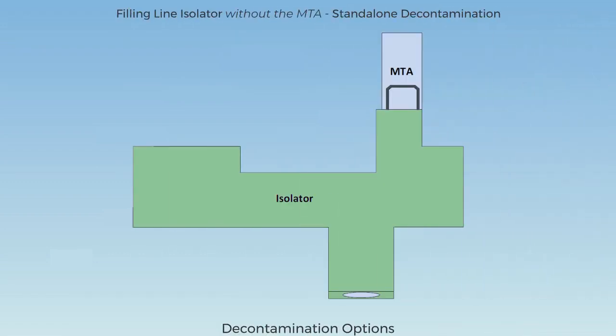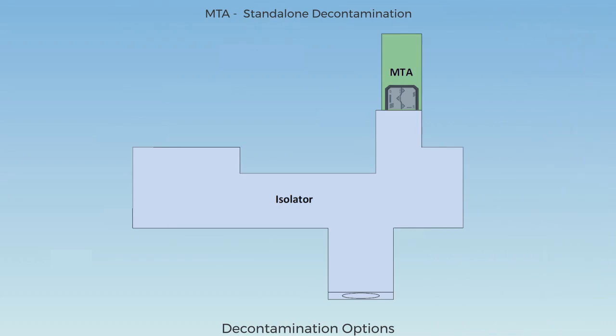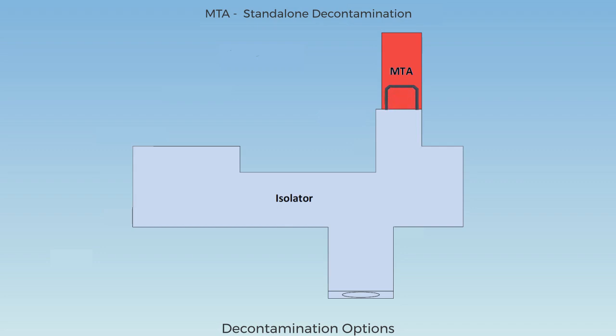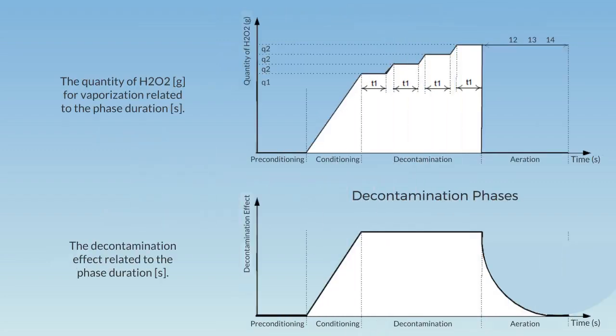The next decontamination option is the filling line isolator without the MTA. After start of the standalone decontamination cycle, a leak test will be performed. The transfer door is closed, and the filling line isolator starts with the decontamination cycle. The MTA can be decontaminated independently of the isolator as a third decontamination option. After successful completed standalone decontamination, the airlock goes into the airlock standby mode, and the transfer door can be opened. During the H2O2 surface decontamination, the desired microbial reduction is achieved by the release of gaseous H2O2 into the isolator chamber and the induction of the lethal dose over time.